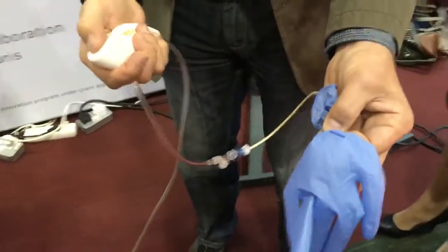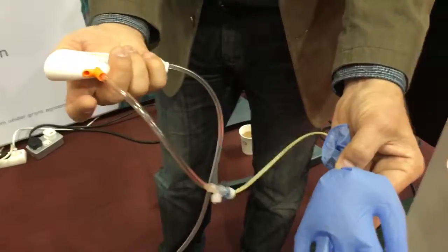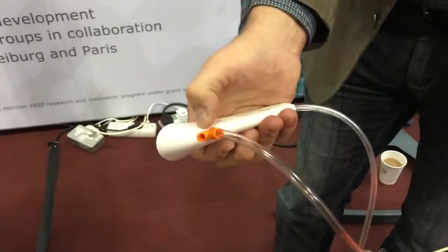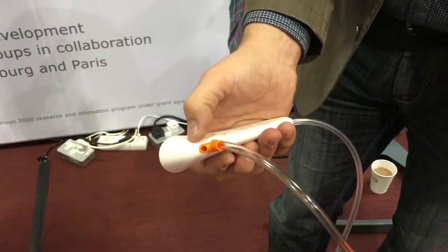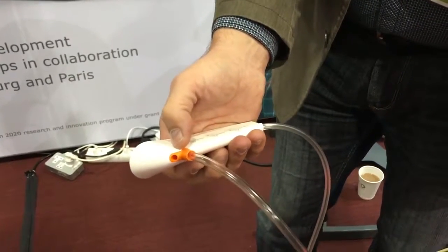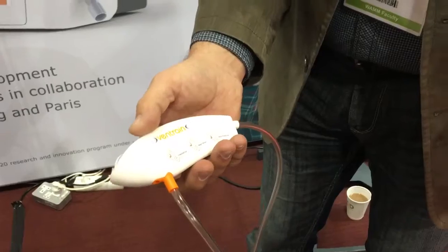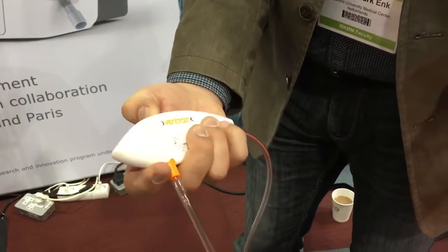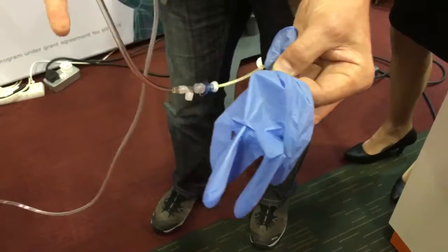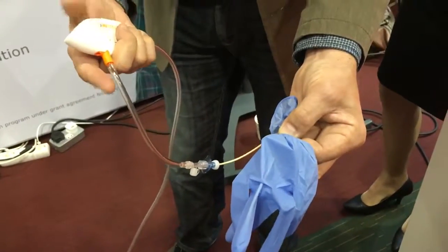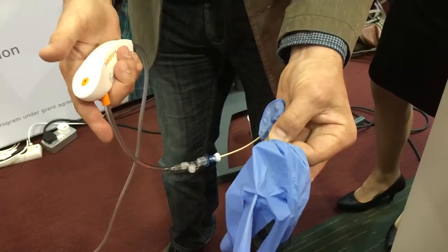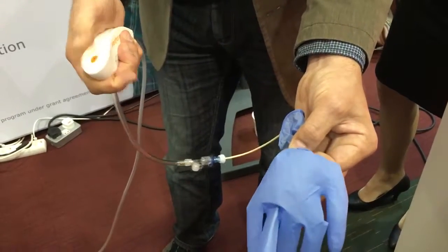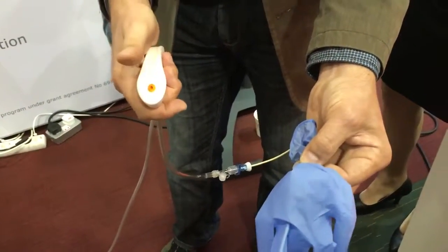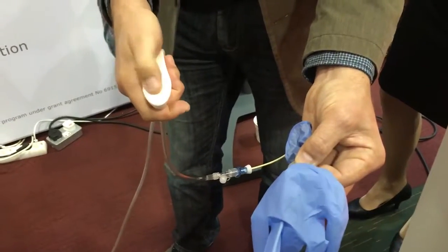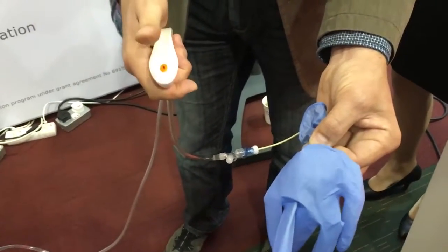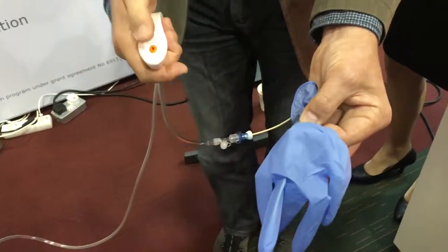Right? And you see, the device is activated by occluding this. If this opening, the so-called on-off switch, sort of a bypass where air is expirated from the outside, is open, the device is functionally switched off. When I occlude this opening, it will start to suck, as you see here. And if I simultaneously occlude the on-off switch and the outlet, I'm redirecting the flow set at the flow meter to the patient. And there's a simple sort of, I shouldn't say simple because it's physics that I don't understand. So what's the effect that gives you that sort of expiratory phase here?